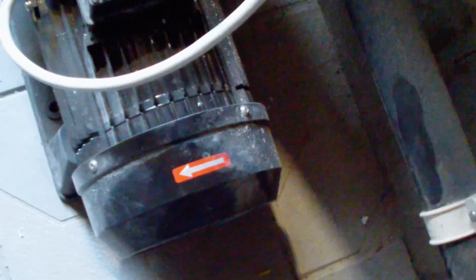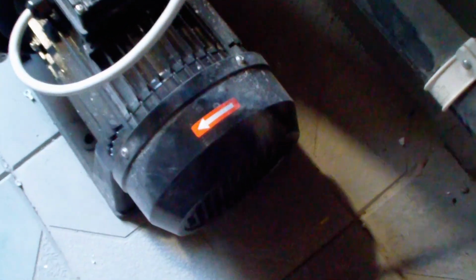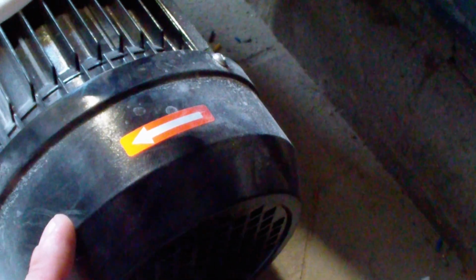So, what do we need to do? We take a wire, preferably a thin one, carefully insert this wire into the cooling grid of the motor, then turn on the pump for a short time. The motor is rotating in the wrong direction. I see that the wire has been pulled in, and the arrow shows the direction of movement here. Therefore, we will do phase reversal.